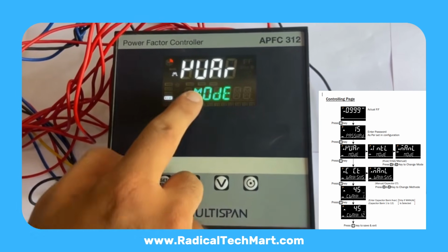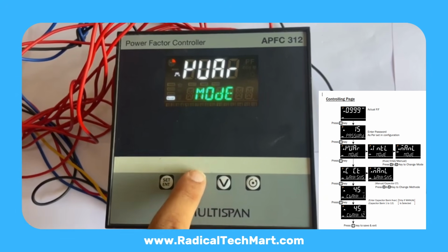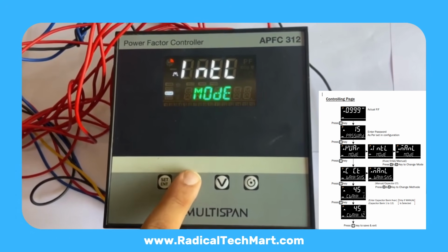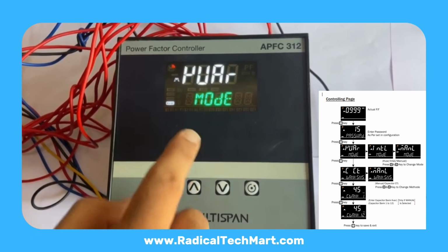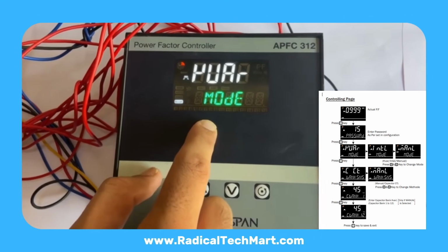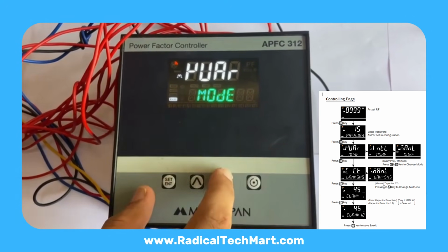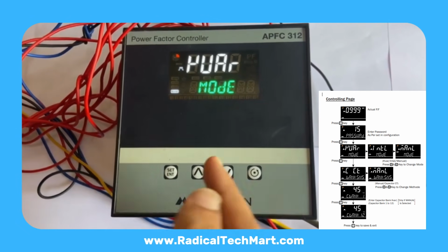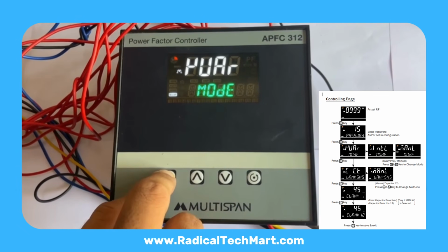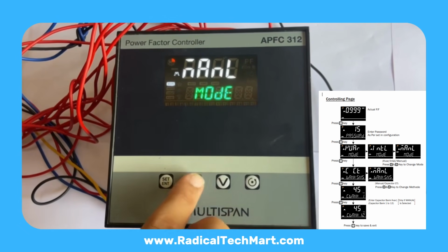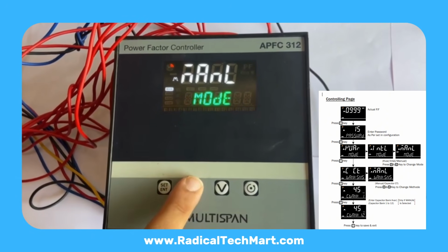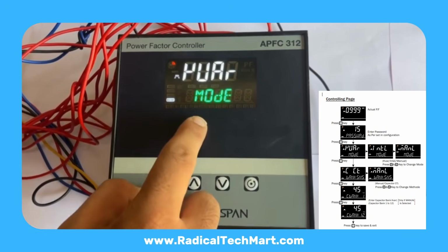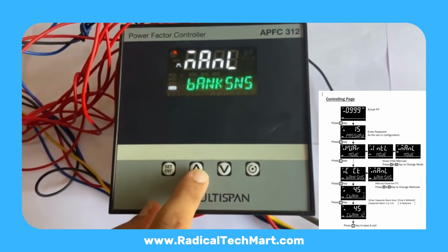You will now see 3 operating modes. Kilovolt ampere reactive mode achieves your set power factor in a single step by selecting the closest capacitor value. Intelligent mode switches capacitors step by step to reach the target PF smoothly. Manual mode: you can manually turn on or off each capacitor step using the arrow keys. Select the mode you prefer and press set.